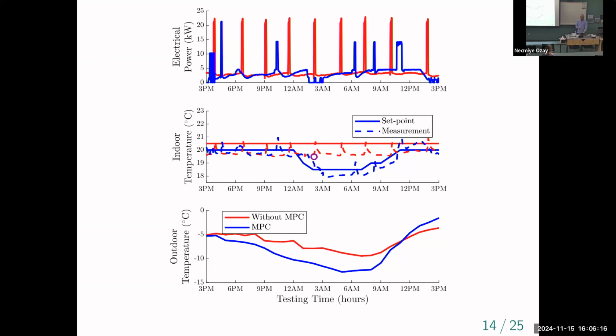So you can see here that the device level control system tracks the actual set point, but typically with an offset of about 1 degree Celsius or about 2 degrees Fahrenheit. So it has, if you like, a steady state error term. Nothing really we can do about that. That's kind of the manufacturer controls. And you can see that the weather conditions under kind of our baseline day, the red day, are a little bit warmer than they were under the MPC day. So this is a more challenging control problem for the predictive control than it is for the baseline control.